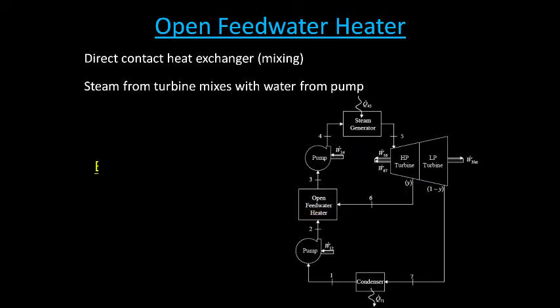Now, what are the benefits of doing an open feed water heater? Well, one of the key benefits over the closed feed water heater is that it's simple and inexpensive. It's a very simple system to put together. But a big benefit beyond just heating it up and possibly improving your efficiency is that it de-aerates the water. What we mean by that is it's going to remove unwanted gases, O2 and CO2, those kinds of things that can get mixed up in your flow as things churn around. And the reason it's able to get rid of them is that the flow comes in here at higher than atmospheric pressure, and so you have a means for the excess gases to just flow out of the system before we continue on up to the second pump.